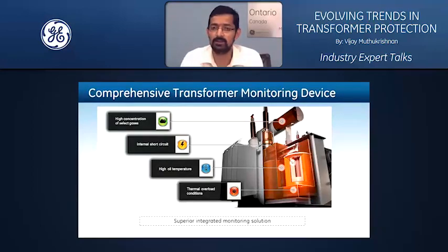You can bring in your tap changer inputs either through a potentiometer, through BCD digital inputs, or using a DC milliampere input. When you step back and think about it, today you may have multiple devices along with the protection relay to do your protection plus monitoring and control functionalities. Now we are saying a single device such as an 845 transformer protection relay can give you a very comprehensive integration of these functionalities, eliminate the discrete devices, and offer you value which will be very powerful along the life of the transformer.